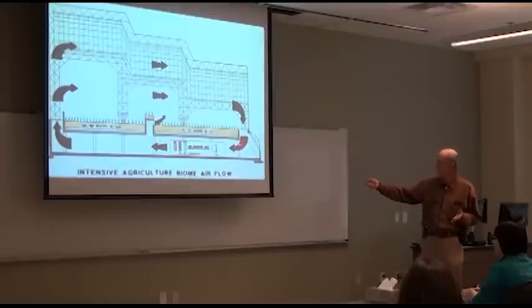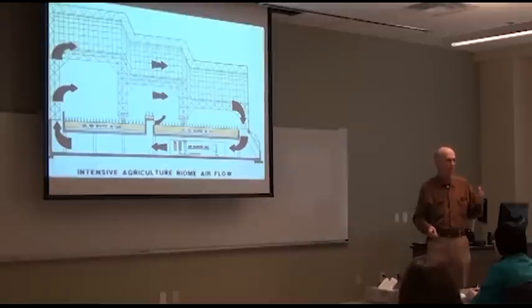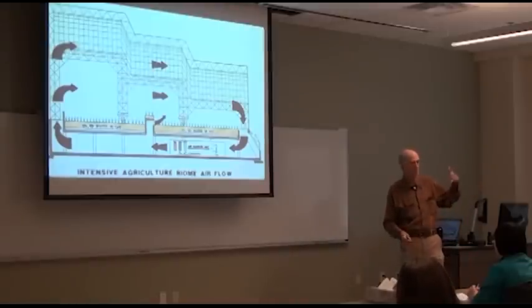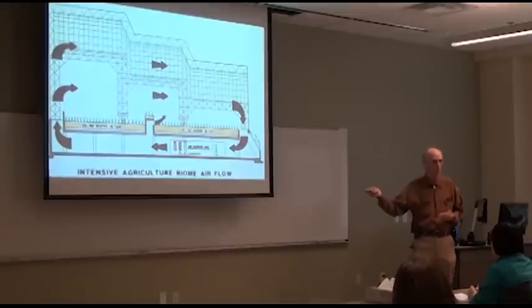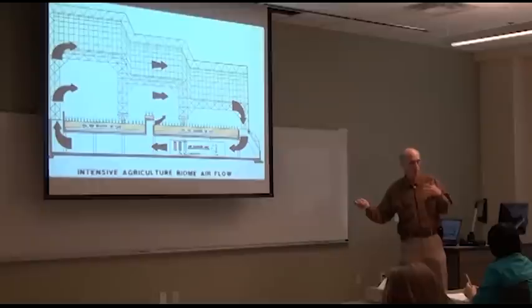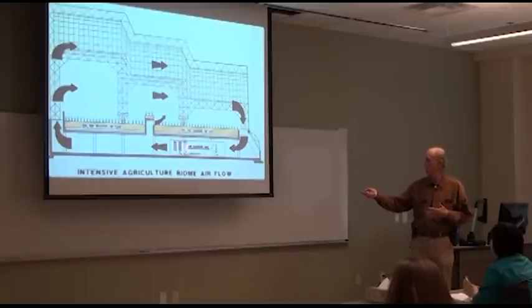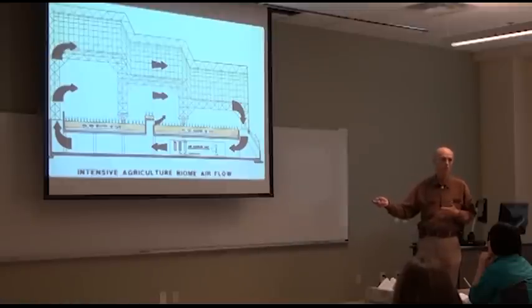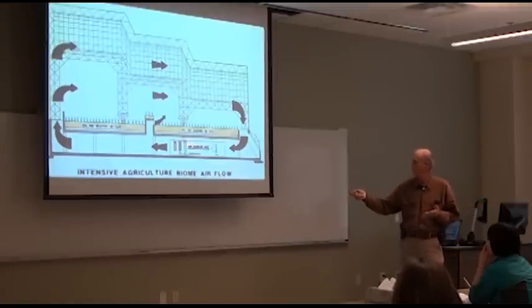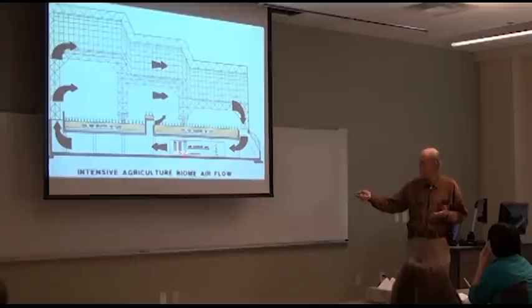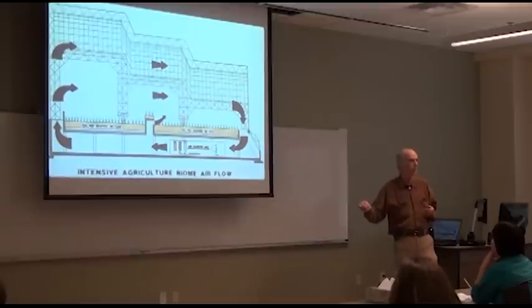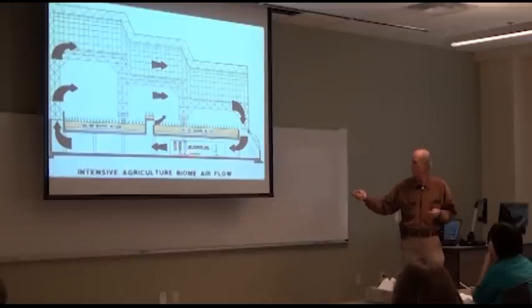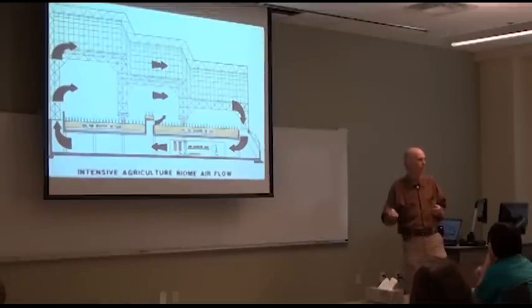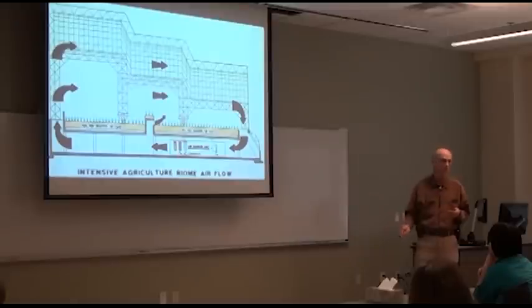This is this large air handler I mentioned before. It is sucking air in with a fan. The first coil that it encounters, which is like the radiator of your car, that is that outside water from the energy center is circulating in that coil, but it's not leaking water into Biosphere. It's just carrying the heat, cooling or the heating. The air touches this first coil, which is just evaporatively cooled water, maybe 45, 50 degrees. The air is cooled partially. Then the air is cooled by chilled water. And you see these drips in the diagram there that represent the condensation that occurs because of the cooling of the moist air on the coils. And that's how we recycle the water inside Biosphere 2 by collecting it as condensate on the cooling coils.